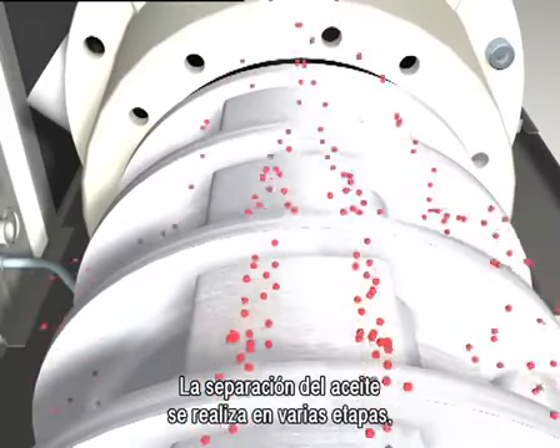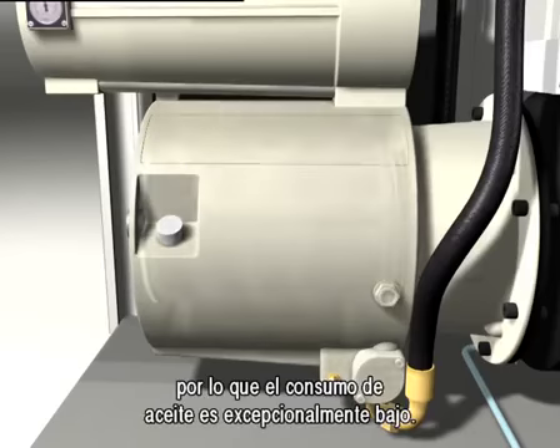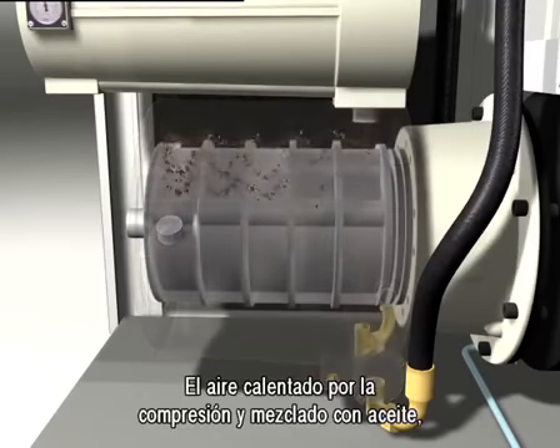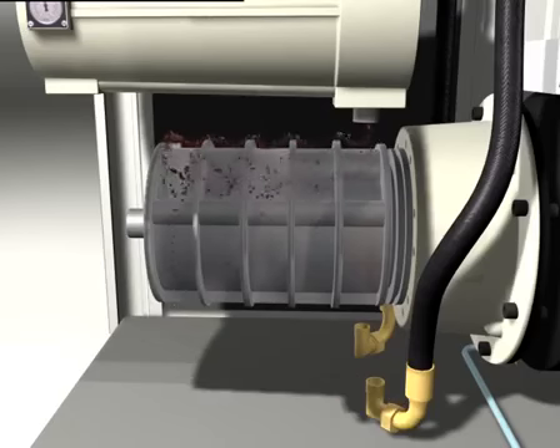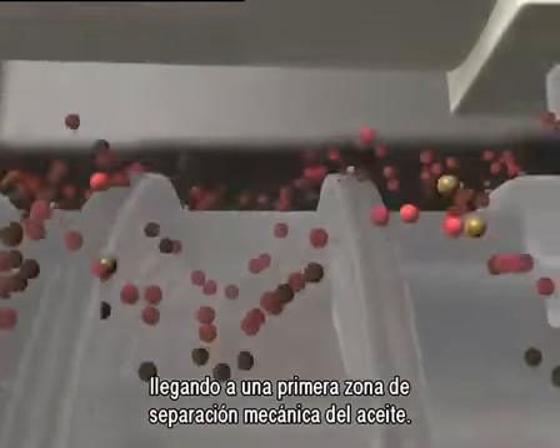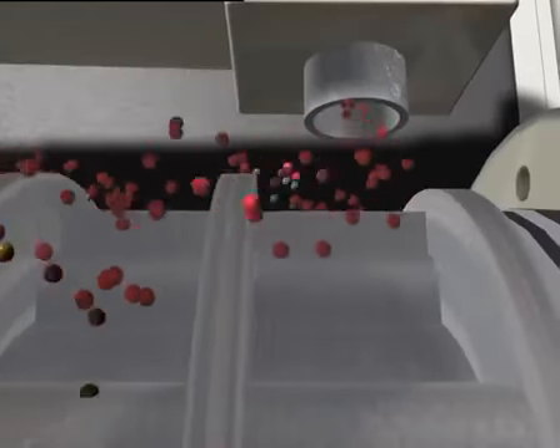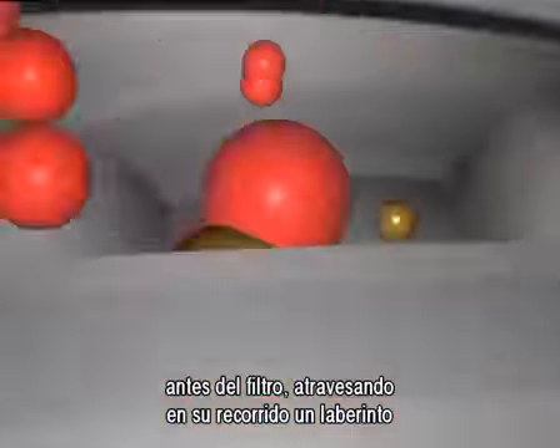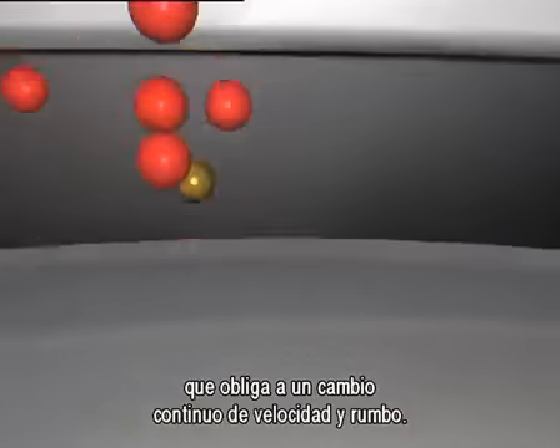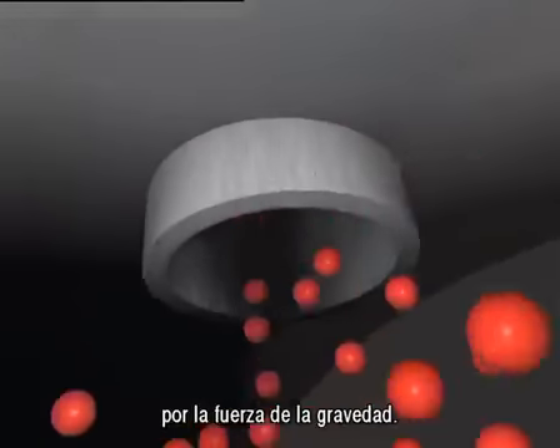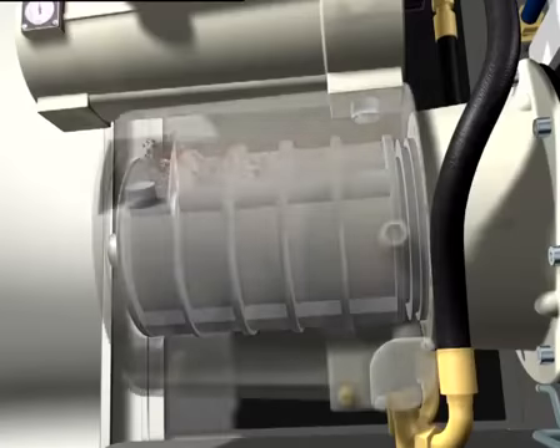The air-oil separation occurs in subsequent stages and ensures exceptionally low oil consumption. The hot compressed air mixed with oil passes through the exhaust ports where the first mechanical oil separation stage occurs. A second separation takes place at the final separator inlet before the filters through a labyrinth path due to changes in speed and direction. During this phase, the oil particles tend to drop down because of the force of gravity.